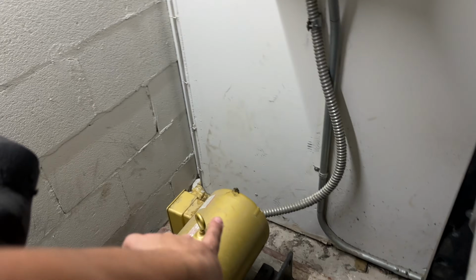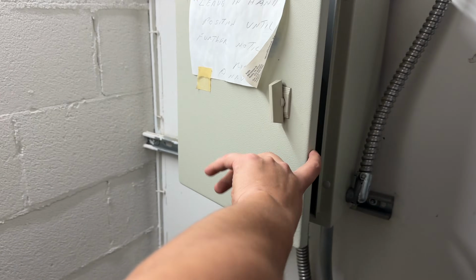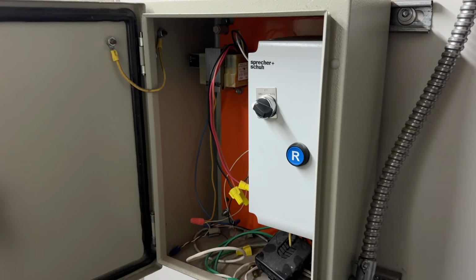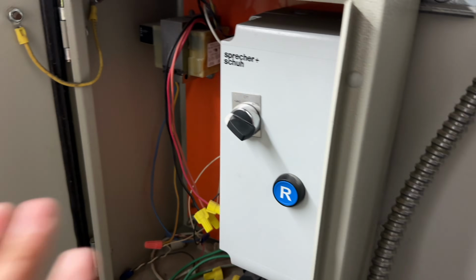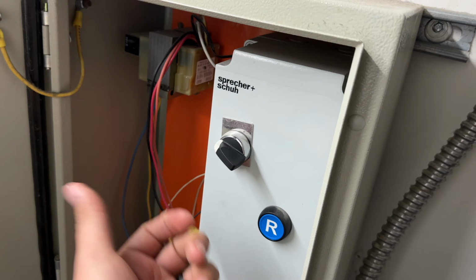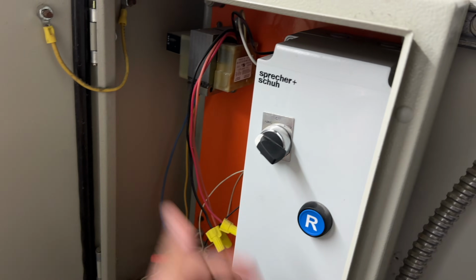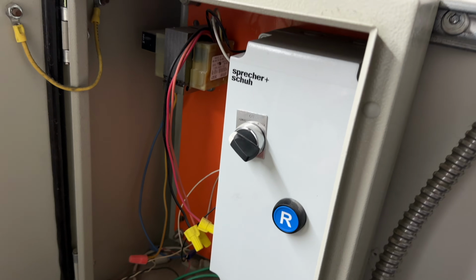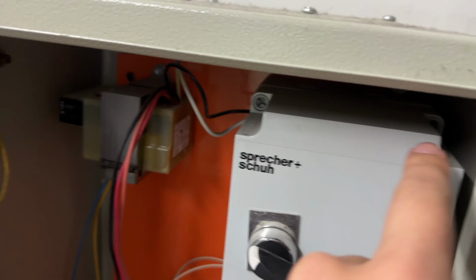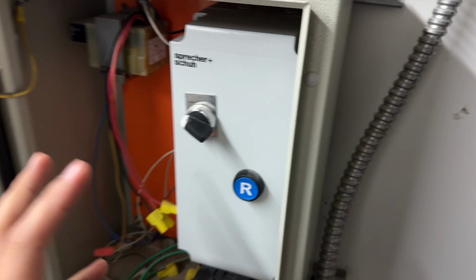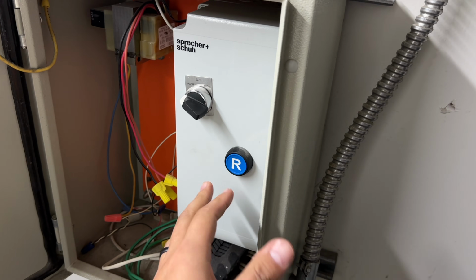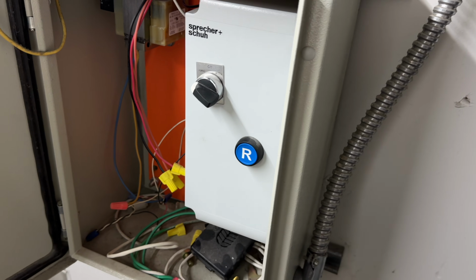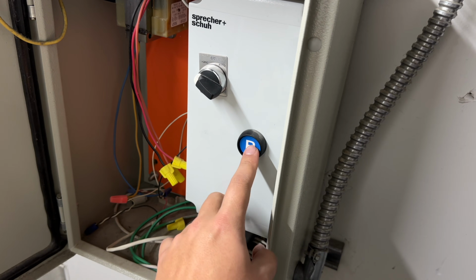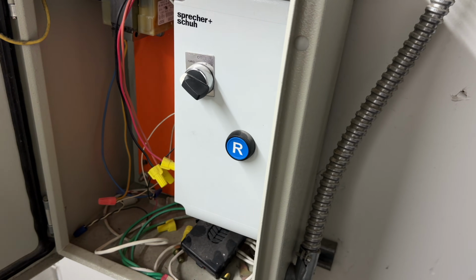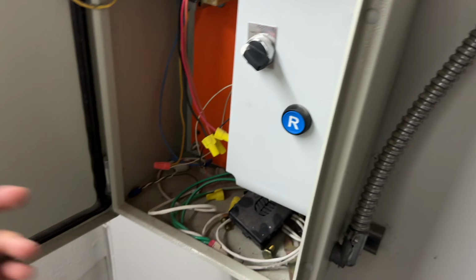And I came here, traced it back, goes into this starter right here. They always want this in the hand, so I turned it off, turned it on, didn't do anything. I reset this, didn't do nothing. I actually, there's 4 screws on top and bottom. Took this whole cover off, and I actually had to reset the actual contactor that's inside there. This button doesn't even work for some reason. It doesn't make good contact, so I pushed it, motor kicked on.